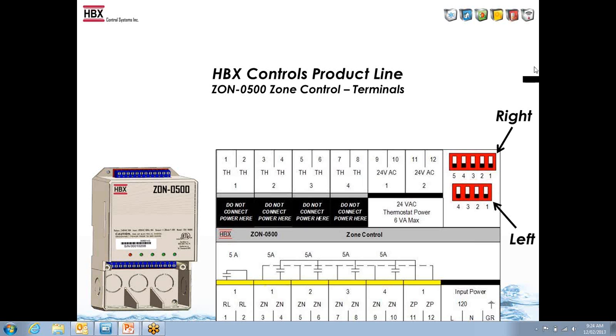The one thing about the Zone 500 is that you can have different priority options. So you can have regular domestic hot water priority, where Zone 1 prioritizes over all the other zones, even if there's more than one connected together. Or you can have Zone 1 and 2 priority over Zone 3 and 4. If you have more than one Zone 500 together, you can have one module prioritize over another. Now you don't have to do a bunch of interlocking with relays where you can run the priority sequences straight from the Zone 500.